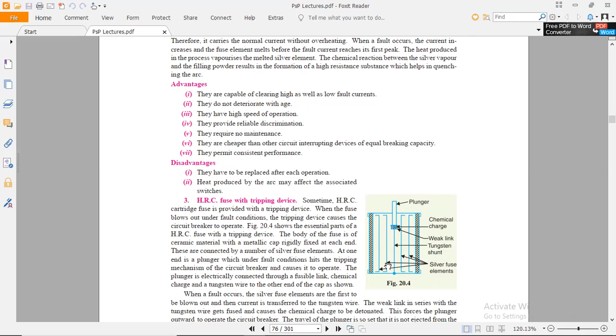The body of the fuse is of ceramic material with a metallic cap rigidly fixed at each end, at this end and this bottom end. These are connected by a number of silver fuse elements. At one end is a plunger which, under fault condition, hits the tripping mechanism of the circuit breaker and causes it to operate.